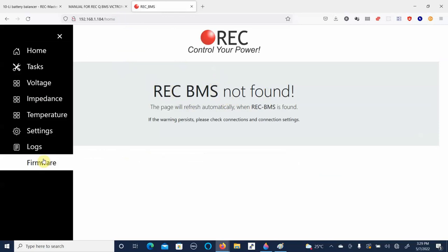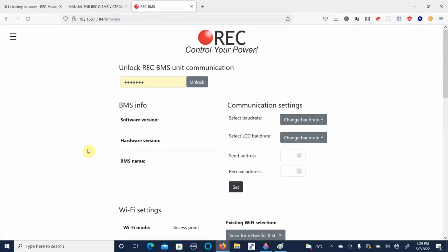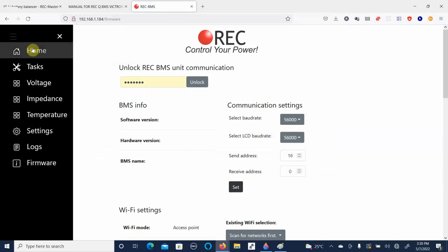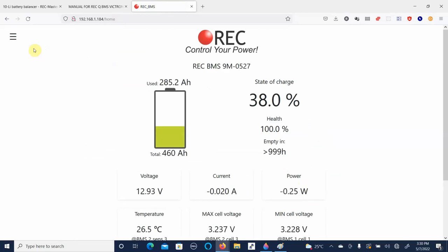So we go down here and go to firmware. And we can see that we need to set our send address and our receive address. The Q series defaults to address number 1. Address number 2 is used for the active BMS, and number 16 is the default address for the master. And in this case, our Wi-Fi is set to number 0. So we set that to 1 and 16. We go back to our home screen, and now we can see that we're connected to device number 16 on the network.